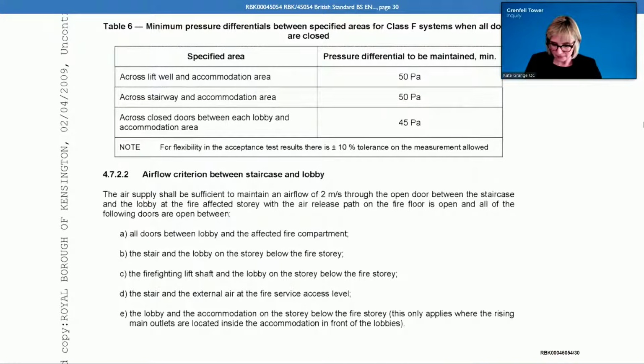But can we agree that if you were doing acceptance testing in accordance with the British standard that's referred to in ADB, you would do those tests with a range of other doors open? Absolutely, yeah. And that's the expectation, because that's what was proposed. Yes. Otherwise, you're not proving the system. Could I just... Sorry, do you want to say something? You showed me another section of that guide of the BS. Was I aware? And I said I don't think so. I don't know whether all the tests there are related to a pressurisation system or a depressurisation system. So I'd just like to make that point. I may have answered wrongly because it may not relate to that type of system. That's all.